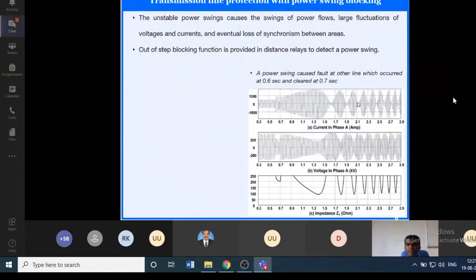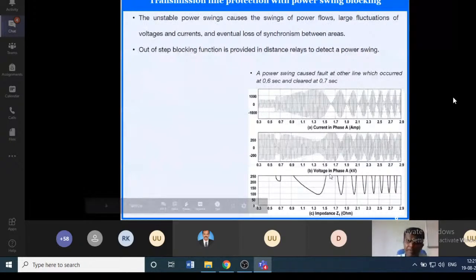When you use the impedance relay to measure the impedance using this current and voltage waveform, the result will be like this. The measured impedance is getting down. We are getting very low values which enter the operating region of the RX plane. That will create maloperation. That can be avoided using the wavelet transform.